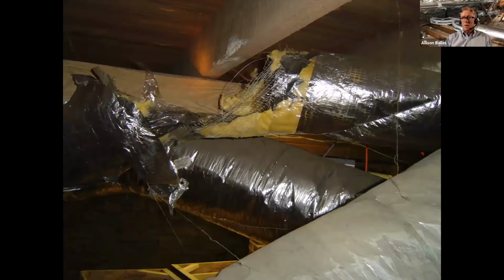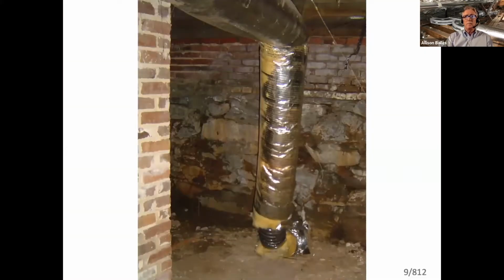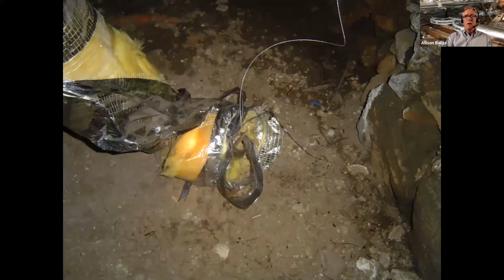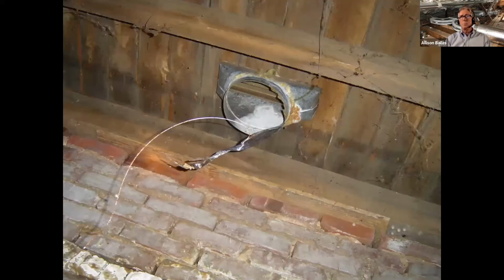Yeah, sometimes there are problems with flex duct, but let me show you the advantage of flex duct, even in a situation like this. Yeah, it's been torn down by some critters in the crawl space, but you see that wire? That's the helical wire that keeps the shape of the flex duct, and it's still attached to the boot, and that's guiding the air to the boot. That's the path of least resistance right there. That's how the air gets to the boot.